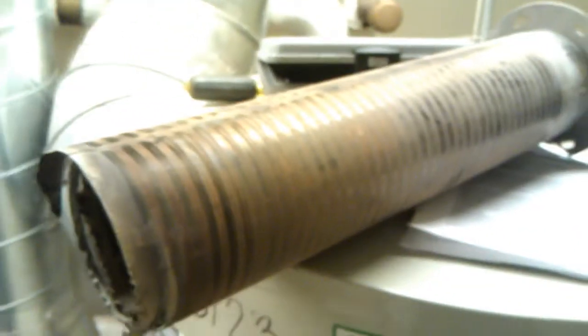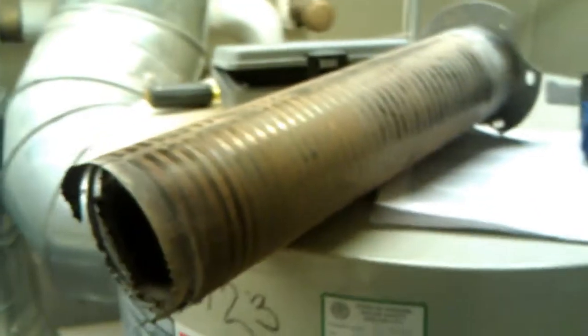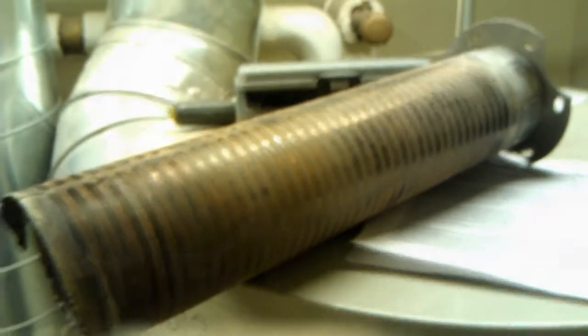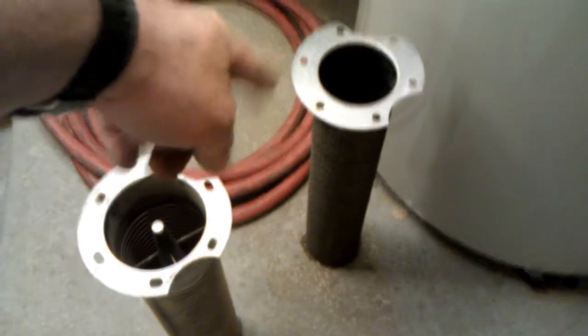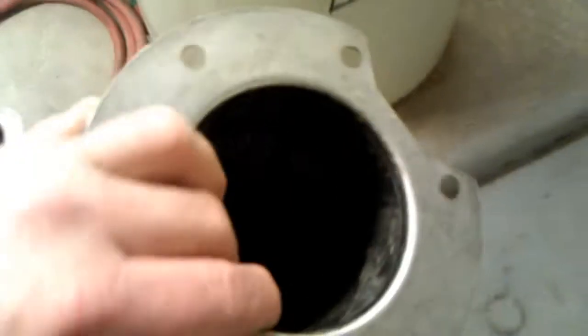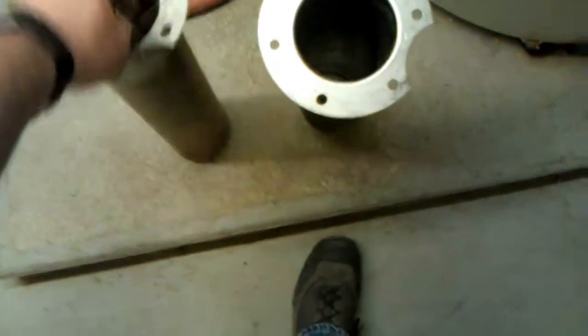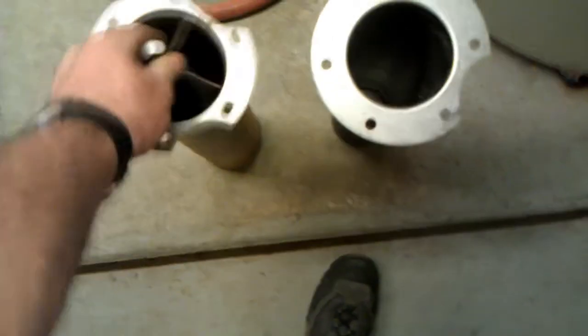I think we got an extra one. We have a boiler we took out when they put this new unit here in. So I'll be able to see if I can take that sucker apart. I had an extra one. This is from one of our newer boilers, the one we pulled out to put this newer Primera in here. It's got the wire mesh style, just like this newer unit does. It's another brand, but it's the same kind of design of burner. It's got the wire mesh, steel braiding or whatever it is. This one doesn't have the pre-filter in it or screen or anything. It doesn't look like that one. It's probably just the first design and this is probably the revision.